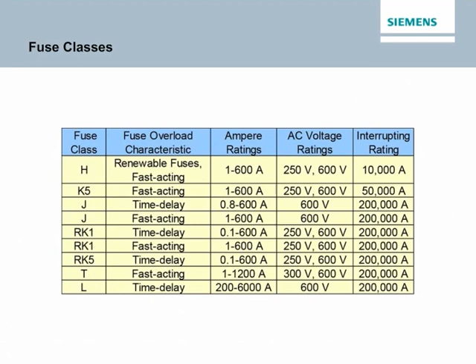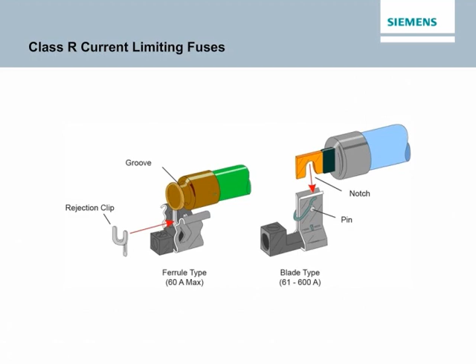The accompanying illustration shows Class R type fuse holders, which feature rejection clips or pins that permit only Class R fuses to be installed. This prevents installation of a fuse with a lower interrupting rating, such as a Class H or K fuse.